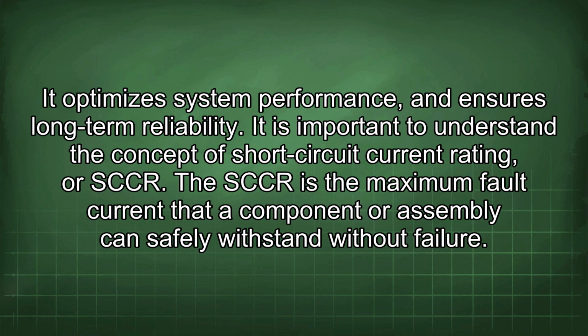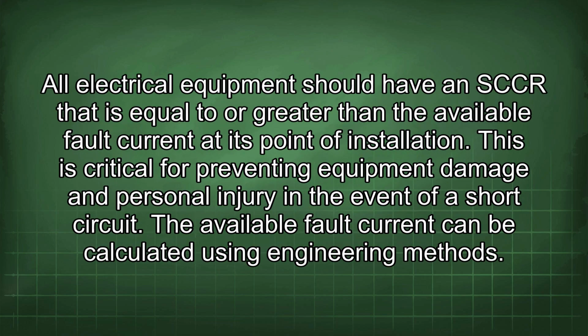It is important to understand the concept of short-circuit current rating, or SCCR. The SCCR is the maximum fault current that a component or assembly can safely withstand without failure. All electrical equipment should have an SCCR that is equal to or greater than the available fault current at its point of installation. This is critical for preventing equipment damage and personal injury in the event of a short circuit.